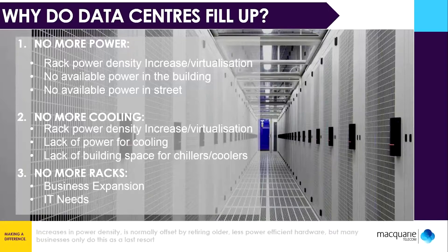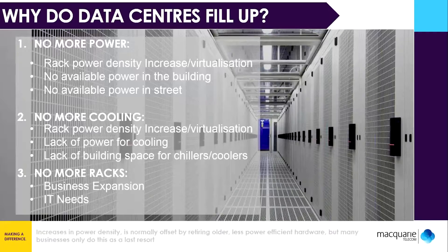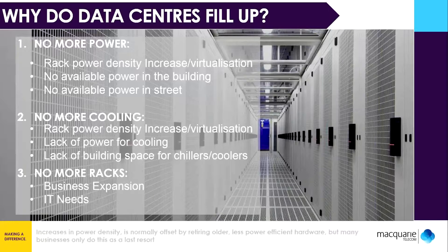Many buildings that support these data centers were never intended to do so. Increasing a building from 2 megawatts to 2.5 megawatts can actually be a huge undertaking — often the power company will require new feeds or transformers, which themselves need space inside the building and can cost hundreds of thousands of dollars. This is all because the density of equipment power is increasing. I've actually seen half-full data centers that have plenty of space but have maxed out their power requirements and can't add any more IT infrastructure.